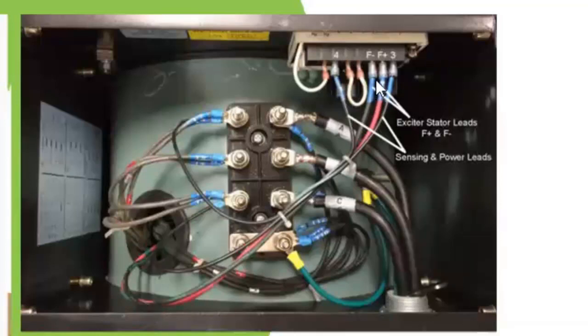So when you disconnect this, you can get your continuity outside, okay? You get your normal resistance if you have been taking resistance reading on the exciter field before. Then you don't expect it to read to ground, okay? But that will be a fault.